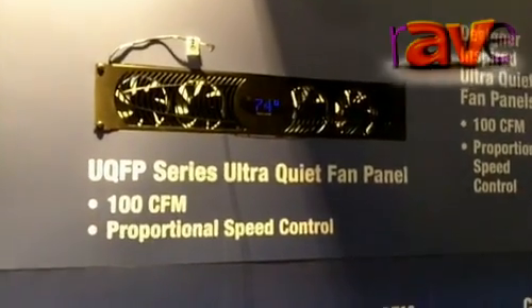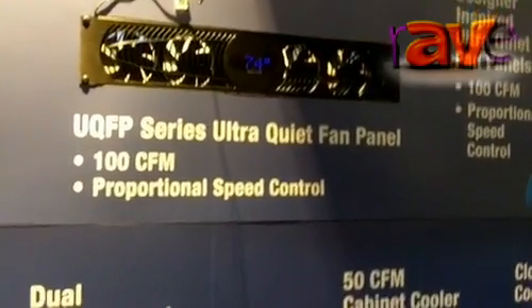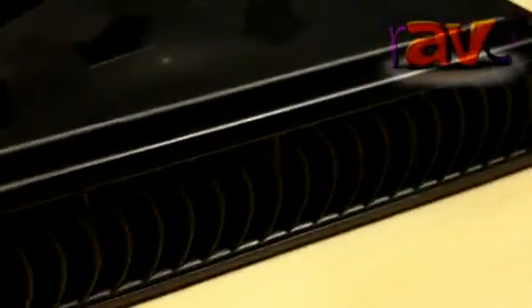So what we did to address that is develop a high static pressure blower. Static pressure means this blower has more capacity to pull the air through in a more powerful way. This is that blower in a component cooler, designed to be placed on top of a hot component and blow the air out.